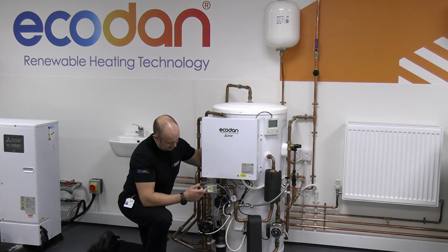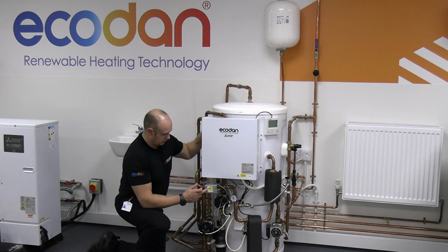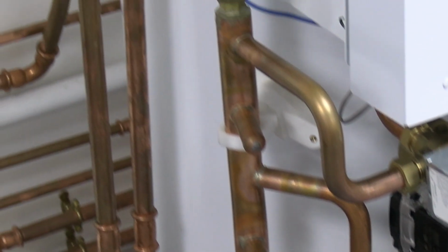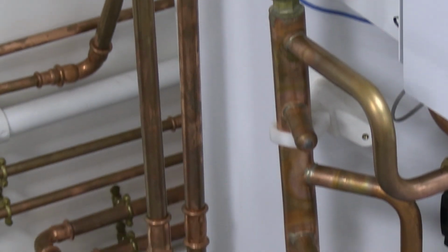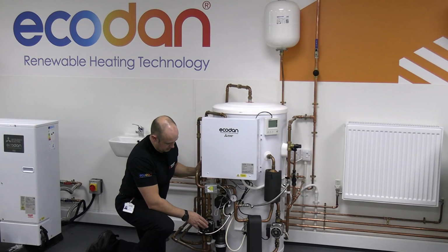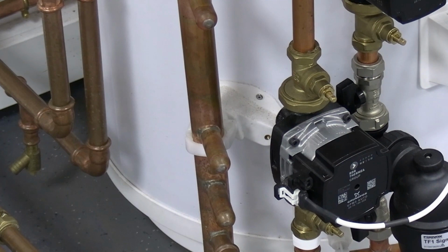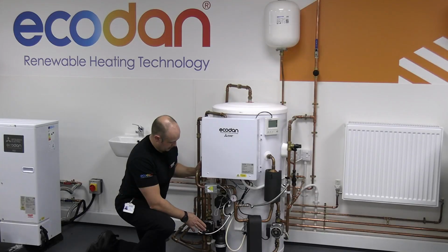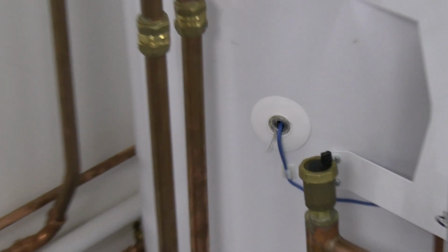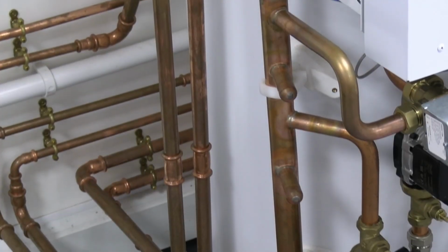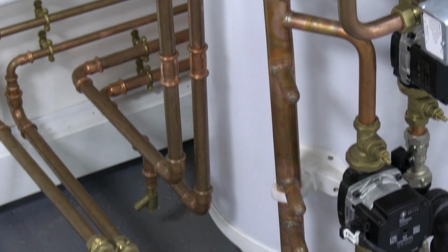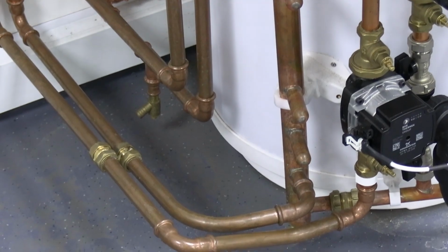Onto the other side, onto the heating side. So follow it around there, we come onto a low loss header. And I've got zone 1 connected onto this particular system. So there's my zone 1 heating pump connected onto that low loss header. At the top of the low loss header, we've got an AAV and we've got a drain point. You can see on the actual low loss header, we've got connections for multiple zones. So we can do up to 2 zones straight off the low loss header.